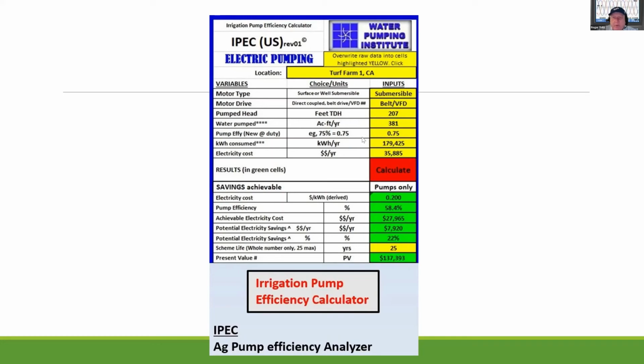You can put in the amount of water pumped. You can look at your pump duty, which comes in at 75%, and then you can go to your power bills and accumulate the total kilowatt hours used annually. Put in your annual utility rates, and it'll automatically run a quick test for that pump and see if there is any potential savings, if there are some losses or not. It's a simple operating tool.